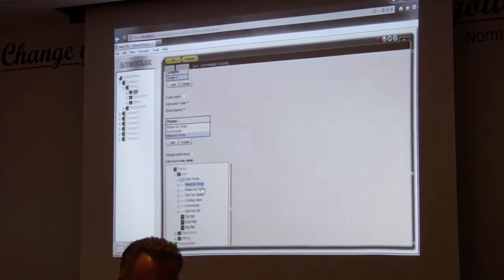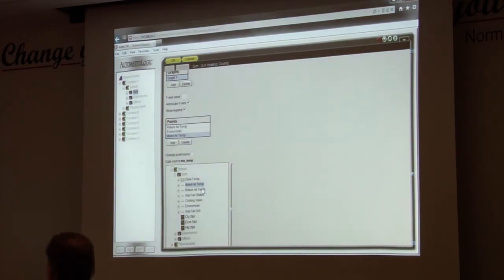Okay, next from the mixed air temp, was I checking the freeze stat? The freeze stat was fine, wasn't it? I don't see it on there. Well, we're going to have to deal with that in a little bit. I'm going to leave a spot because I'm not seeing freeze on here, right? So let me go ahead and just start a new graph.